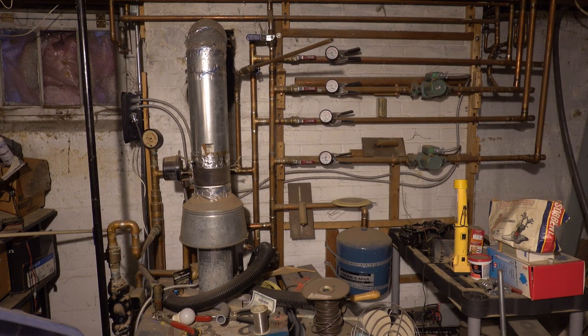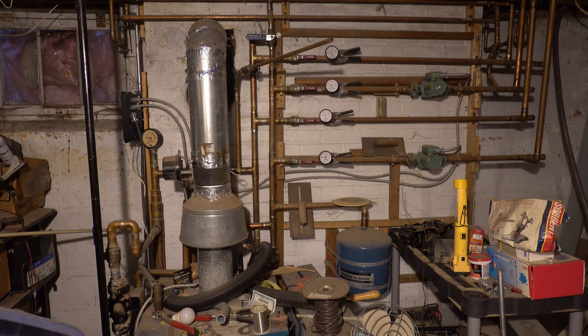This is part of the heating system — it's hot water radiators. I had to replace the boiler and all the plumbing, so all that funky steampunk-style plumbing you see in the back is my particular invention. It's actually pretty sophisticated — there are two different zones with monitors for outgoing and incoming temperature. It's cold enough that the boiler is firing up today, so those noises will be in there. I've learned a whole lot about this boiler; I've been able to fix it and make it better than it was. The only thing I've had to do in several years is clean the electrode when it had issues firing, and that's pretty easy — just a Dremel brush on the flame sensor, so I don't even have to take it apart.